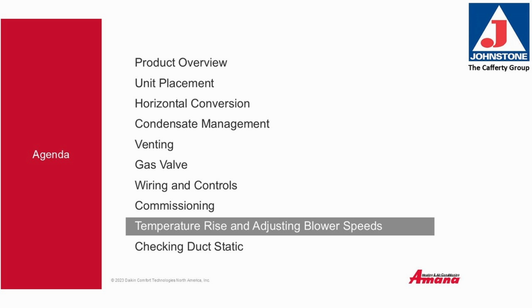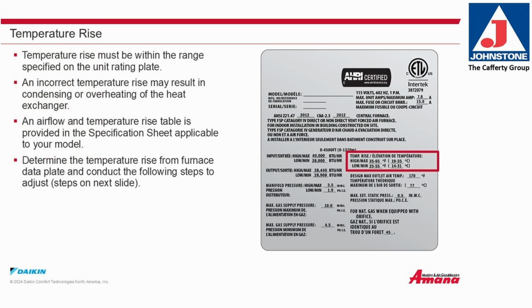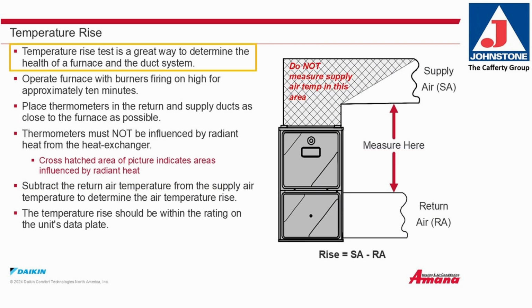Temperature rise and adjusting blower speeds. Temperature rise must be within the range specified on the unit's rating plate. An incorrect temperature rise may result in condensing or overheating of the heat exchanger. An airflow and temperature rise table is provided in the specification sheet applicable to your model. Determine the temperature rise from the furnace data plate and conduct the following steps to adjust to the correct temperature rise. Temperature rise test is a great way to determine the health of a furnace and the duct system.